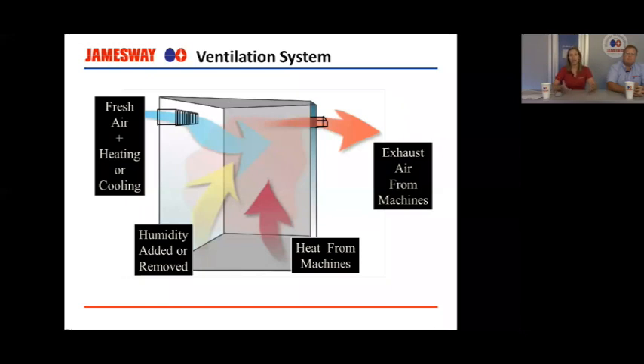So ventilation, how does that work? Basically what we're looking at is the room in front of the machines. We have fresh air coming in to satisfy the oxygen needs of the eggs, which is either heated or cooled. We're adding or removing humidity. There is heat off the front of the incubators and hatchers, heat gain to the room. And then we have the exhaust air off the machines. And this is what we need to balance in HVAC in order to make sure that your room is operating perfectly at all times.